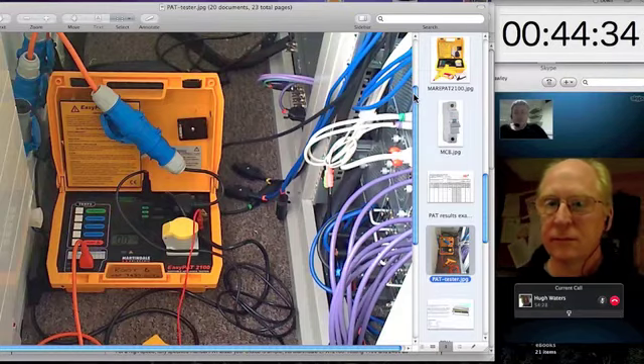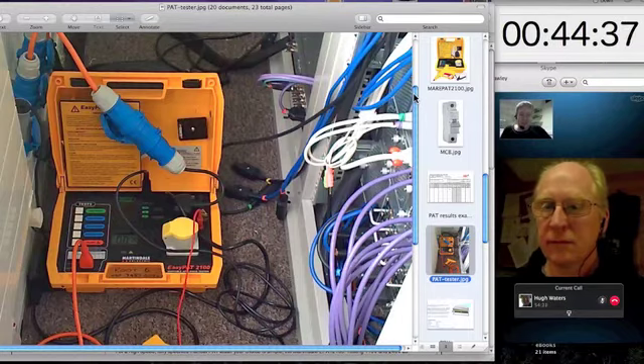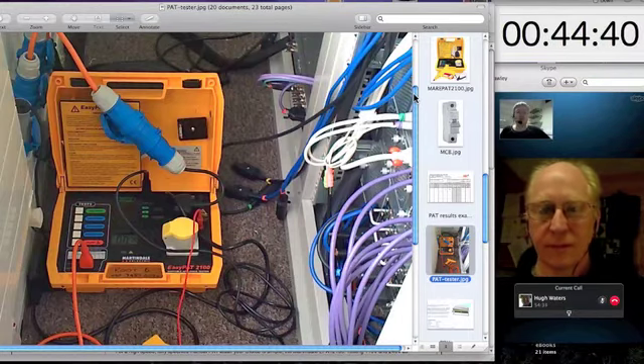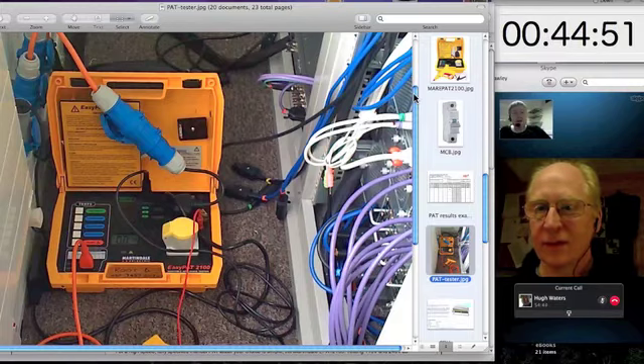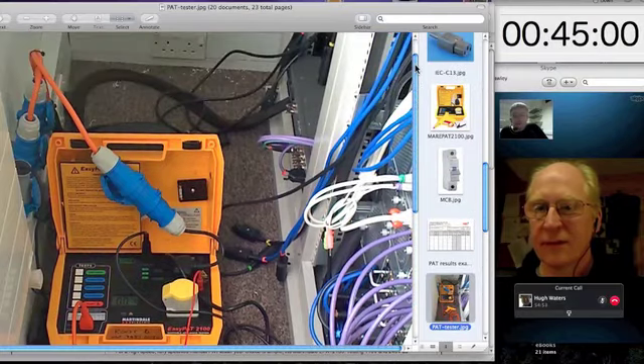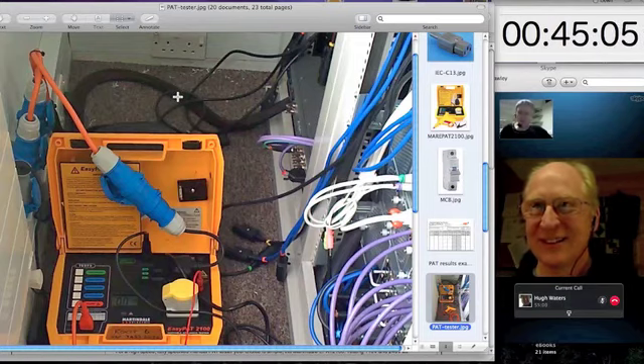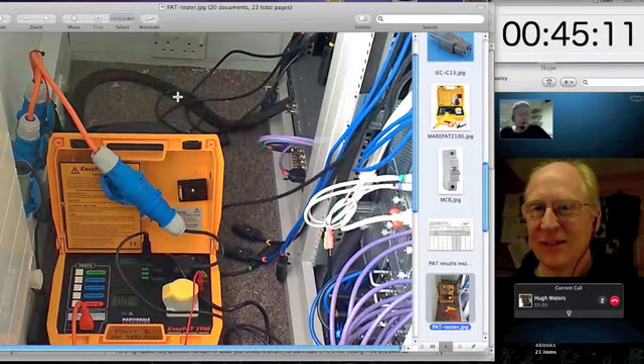And in the same way that we mentioned the demarcation between the electricity company's feed into your building, that big 100 amp fuse in a domestic premises, and those three big 200 amp fuses in a three-phase professional premises, when you build machine rooms, you have a demarcation at each cabinet, and that typically will be the 16 amp CEE-form connector that powers the cabinet. Now you say, well, Phil, you've mentioned 16 amp CEE-form connectors an awful lot. Why are you so obsessed with these things? And I think actually they are a fantastically neat way of maintaining that segregation between technical and domestic supplies.